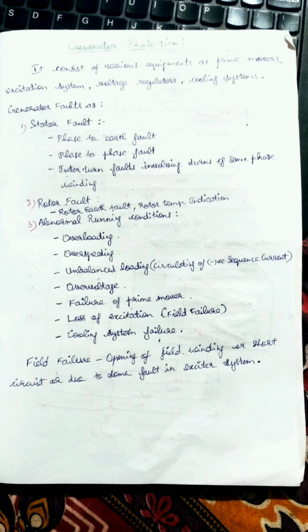The field failure is sensed by keeping a CT in any one of the phases. The CT will be connected to the field failure relay. In this way the field failure protection will be carried out.